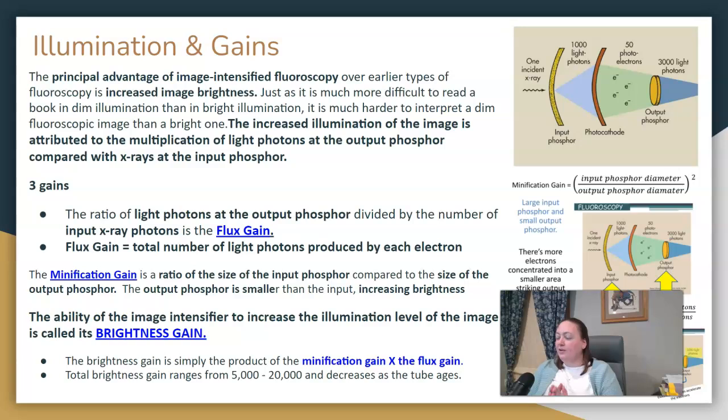And then there are three gains that are involved with fluoroscopy. The first one is called flux gain. And this is a ratio of, they take the number of light photons at the output phosphor, and they're going to divide it by the number of input x-ray photons that we had at the input phosphor and do a comparison of the two.